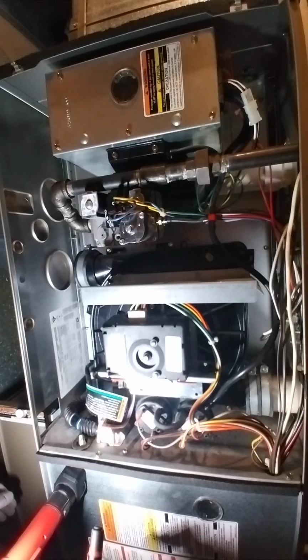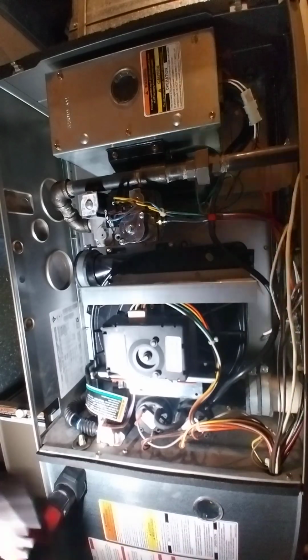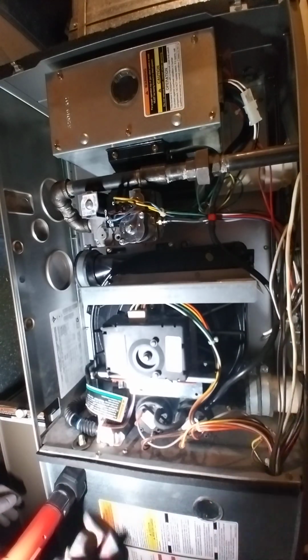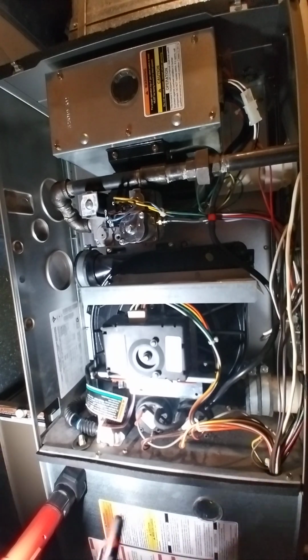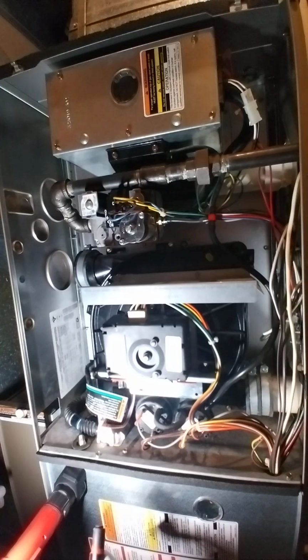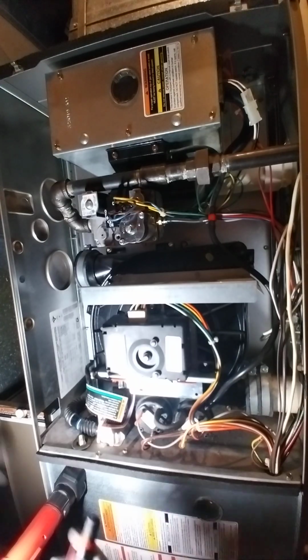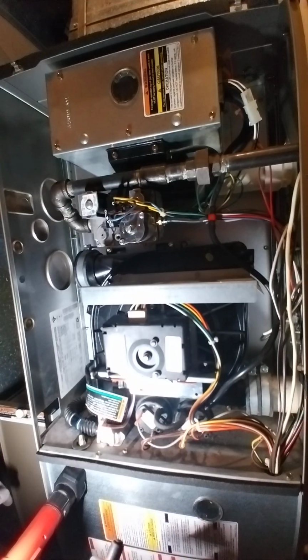And about 10-20 seconds later, it would fire back up in low mode, go to high heat mode, and then all of a sudden it would stop. And eventually that short cycling would also stop because the house would get warm enough where it only needed to run in the low heat mode. So I'm a curious guy, I'm a DIYer, I have some history with automation and PLCs and stuff like that. So I wanted to see if I could sort out what this problem was.